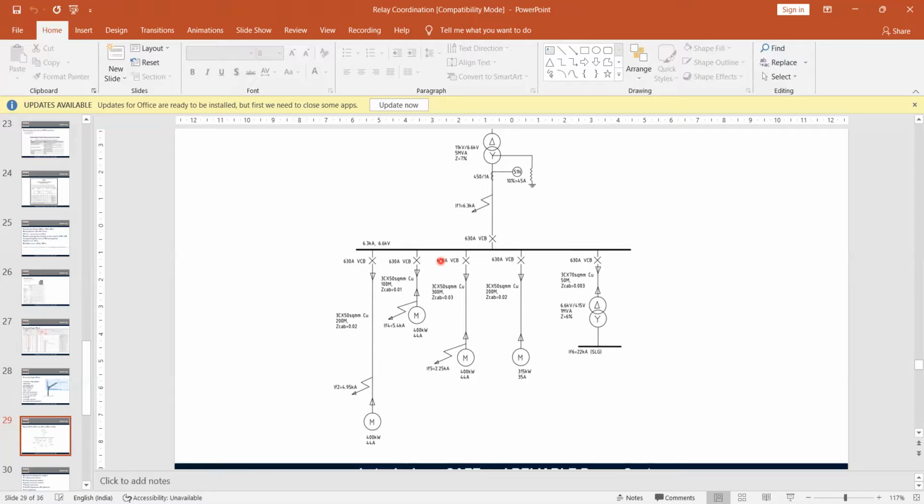It is the 10% pickup current. Of which one? That is the total 10% pickup of the motor, I think, or transformer. The 5 MVA transformer at 6.6 kV was how much? 430 amps? No, sir, 437 amps. Okay, 437 amps.